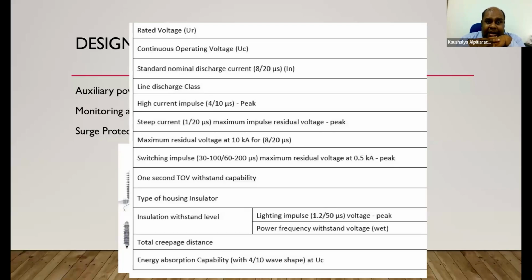And there are so many things: rated voltage, continuous operating voltage, that is the UC, and that will differ from design to design or distribution to distribution, depending on whether you have a directly earthed system at your substation, or whether you have an open delta connection, or a system that is unintentionally earthed. So depending on that, your UC value will differ. To select that UC value, you may have to use higher UR values. So that has to be looked at. The tables in 60099 are very straightforward. You have some classes, line discharge classes, whether it is heavy discharge or light discharge, and so on. So just visit the standard and you will see, it is very straightforward.